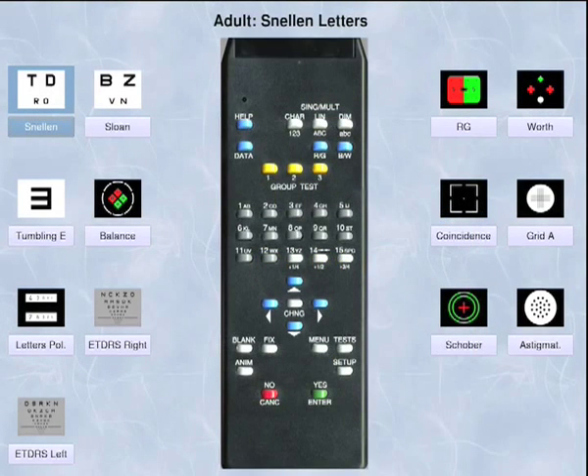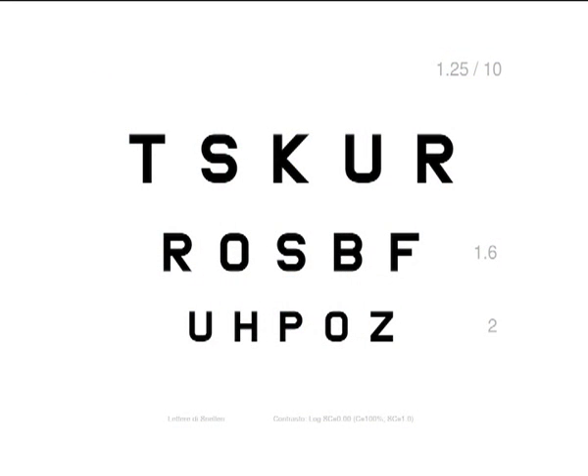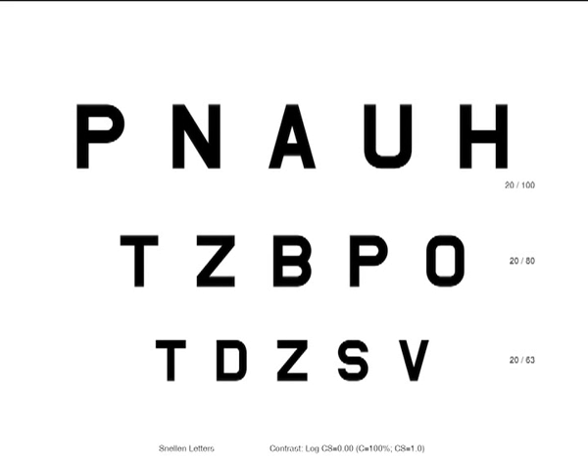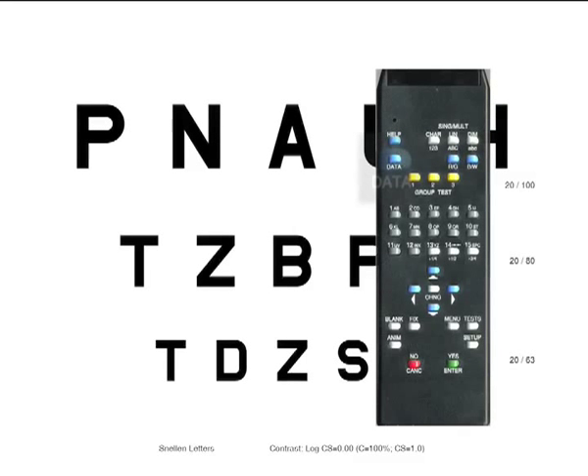Select the test and press change in order to start it. The test comprehends three eye chart lines with increasing visual acuity value. In the right edge and in the bottom are shown the data related to the displayed table. In order to display or hide this data, press the data key.